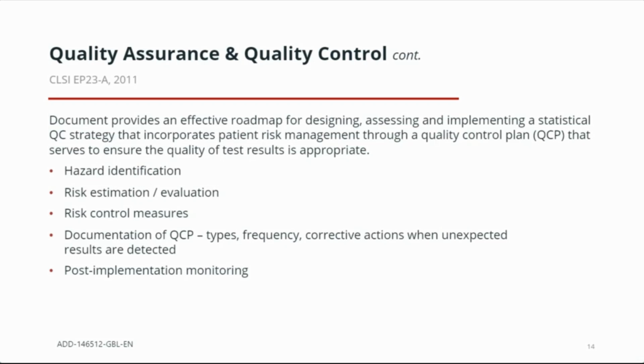Keep in mind that the process is iterative, meaning we have controls in place, then a failure occurs, we need to assess and identify if we have a new hazard, determine if there's an increased severity or frequency of that hazard for failure, meaning erroneous results. And then we work to implement additional risk prevention and control measures.